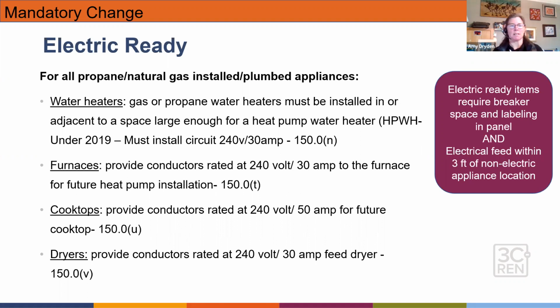In addition, the 2022 code has now addressed these other end uses: furnaces, cooktops, and dryers. This probably looks really familiar to any REACH code you may have been party to or needing to comply with under 2019. Oftentimes in new construction, particularly larger production new construction, we'll see cooktops and dryers both have gas and electrical. They'll do dual fuel, so there's a choice there. Now it's required within the code. And for the furnaces, we're looking at making sure we have 240 volt, 30 amp for future heat pump installation. All of these need to be pre-wired. We need to have space in the panel, so we need to make sure that capacity is there. We need to be labeling it for future use. And we want that feed within 3 feet of where that non-electric appliance location is, assuming that it's convenient for the future electric appliance. Next slide.